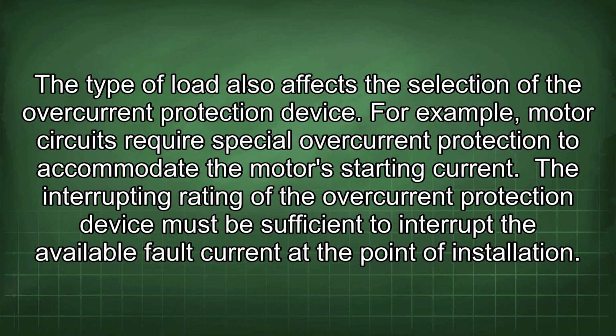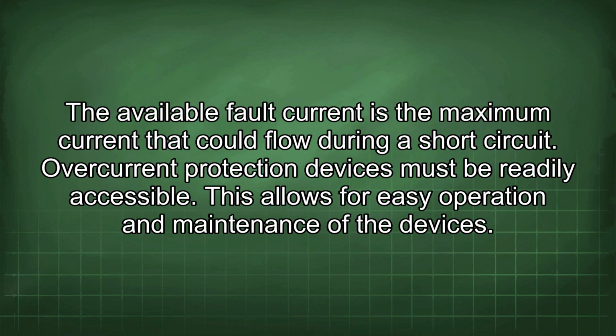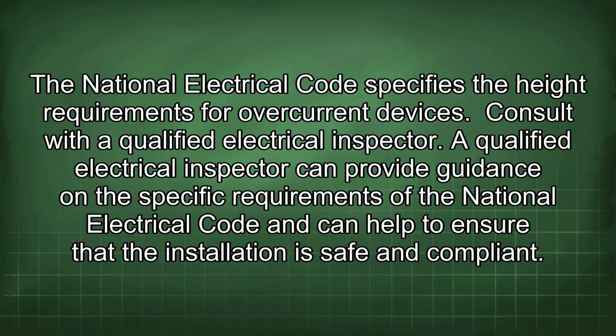The type of load also affects the selection of the overcurrent protection device. For example, motor circuits require special overcurrent protection to accommodate the motor's starting current. The interrupting rating of the overcurrent protection device must be sufficient to interrupt the available fault current at the point of installation. The available fault current is the maximum current that could flow during a short circuit. Overcurrent protection devices must be readily accessible. This allows for easy operation and maintenance of the devices. The National Electrical Code specifies the height requirements for overcurrent devices.